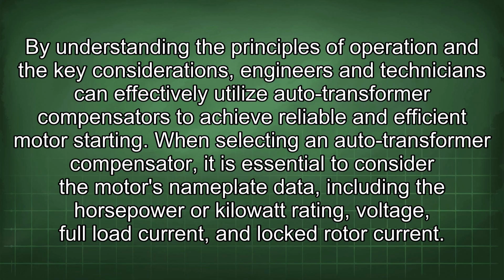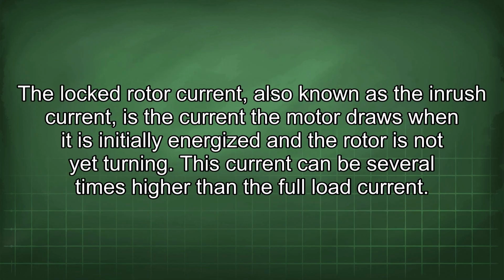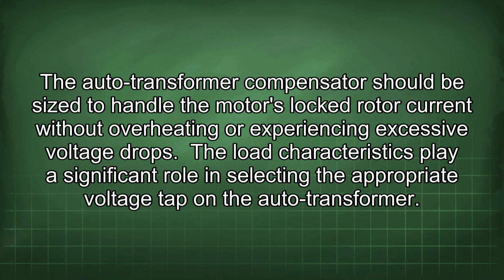When selecting an auto transformer compensator, it is essential to consider the motor's nameplate data, including the horsepower or kilowatt rating, voltage, full load current, and locked rotor current. The locked rotor current, also known as the inrush current, is the current the motor draws when it is initially energized and the rotor is not yet turning. This current can be several times higher than the full load current. The auto transformer compensator should be sized to handle the motor's locked rotor current without overheating or experiencing excessive voltage drops.